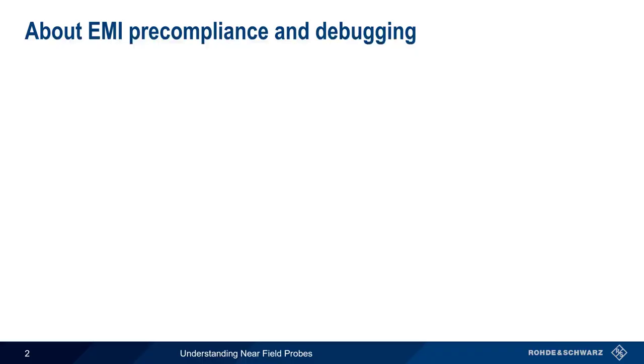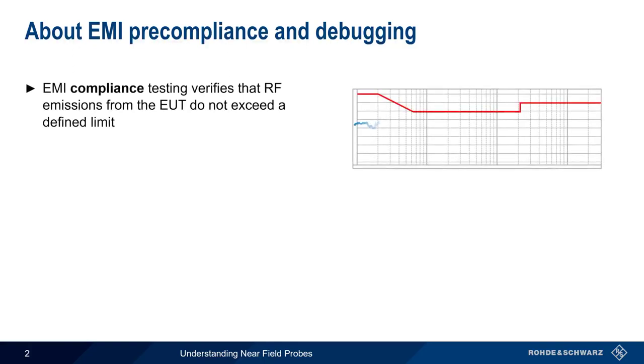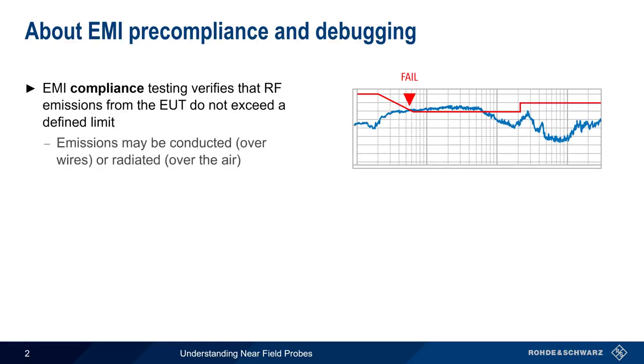As you may already know, EMI compliance testing verifies that radiofrequency emissions from an EUT, or equipment under test, do not exceed a specified limit. These emissions may be either conducted out of the EUT, via wires or cables, or be radiated out over the air.